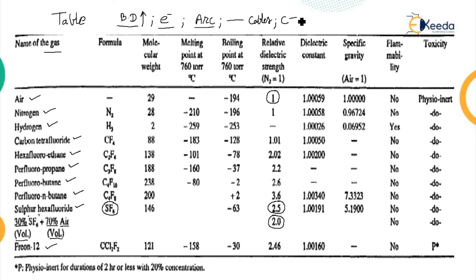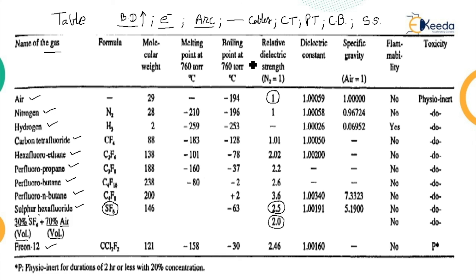Due to its high breakdown strength, excellent arc quenching property, and electronegative nature, SF6 gas is used in cables, current transformers (CT), potential transformers (PT), circuit breakers (CB), and metal-enclosed substations where the gas insulates the entire substation. SF6 is nowadays practically adopted and widely used due to these properties. This concludes the topic of practical considerations in using gas for insulation purposes.